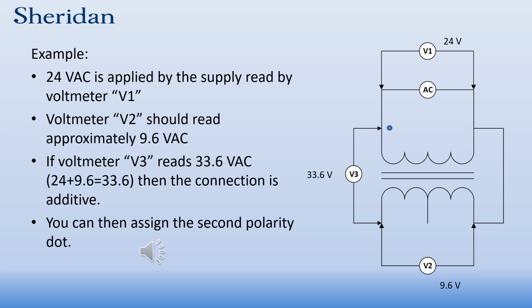The key here is reading voltmeter 3, which, if it's the sum of the two voltages, in this case 33.6 volts, then the connection here is additive, and you can assign a polarity dot. Once you assign the polarity dot, you can then assign terminal designations, H1 being where the high voltage polarity dot is, and X1 being where the low voltage polarity dot is, and then the other terminals.